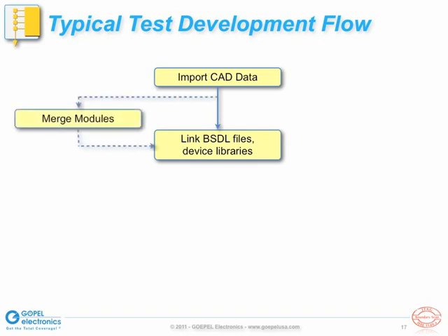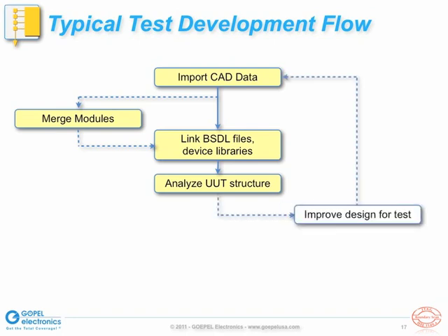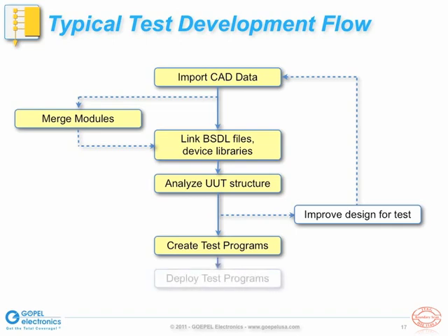In some cases, the UUT may be comprised of multiple modules. The netlist for each module would be imported and the modules would then be merged together. When analyzing the UUT structure, one may identify certain parts of the UUT circuitry that would benefit from redesign in order to improve overall test coverage with boundary scan or other test methodologies. In case of a redesign, the new CAD data would be imported and analyzed. Once we are satisfied with the design for test, we create the boundary scan tests, verify them, and eventually deploy them for prototype verification or manufacturing tests, for example.